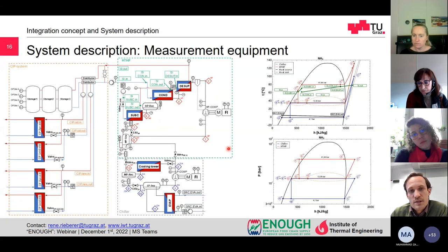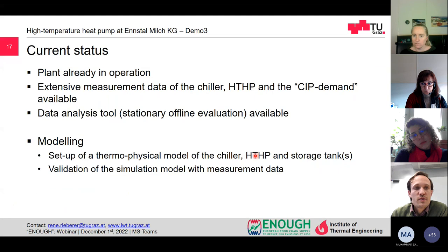And you can also see the process here in this, for example, p-h diagram, on the bottom the chilling process, and on top the process of the high temperature heat pump. Regarding the current status, it's demonstrated that it's already in the field and in operation. So we have extensive measurement data of the chiller, the high temperature heat pump, and the tank.